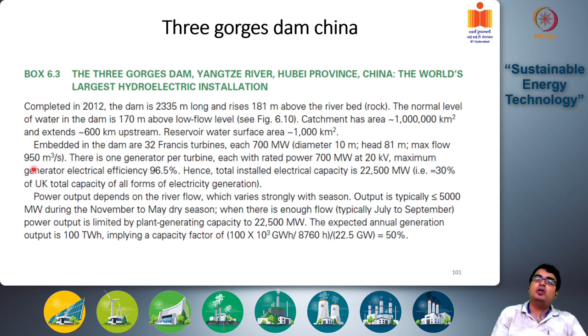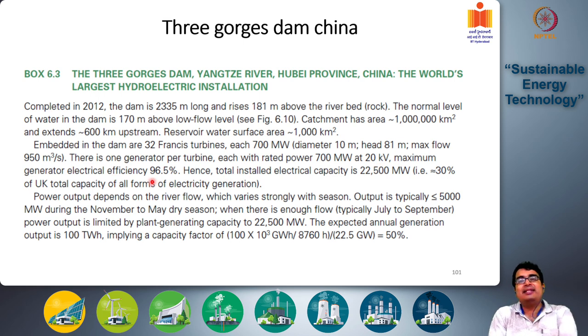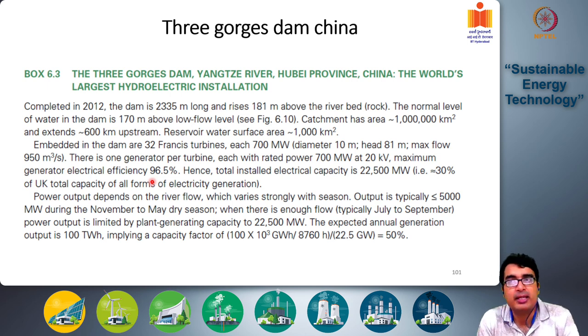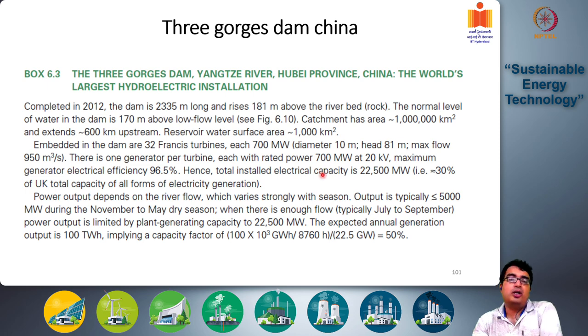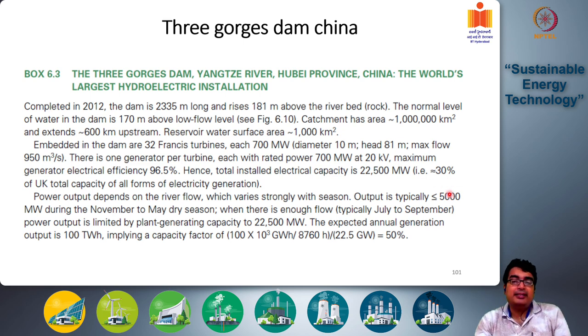There is one generator per turbine, each with a rated power of 700 megawatts operating at 20 kilovolts. The maximum generator electrical efficiency is 96.5 percent, demonstrating that hydroelectric dams achieve extremely high efficiencies of 96 percent or more. The total installed electric capacity is 22,500 megawatts, or 22.5 gigawatts — which is approximately 30 percent of all the power utilized by the UK at that time.